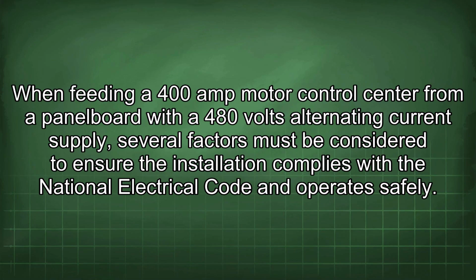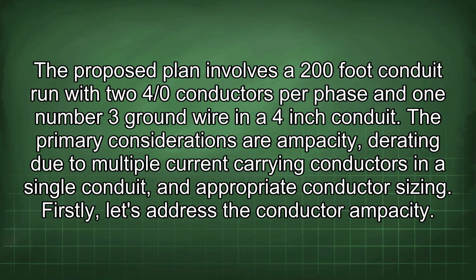When feeding a 400 amp motor control center from a panel board with a 480 volts alternating current supply, several factors must be considered to ensure the installation complies with the National Electrical Code and operates safely. The proposed plan involves a 200-foot conduit run with two 4/0 conductors per phase and one number 3 ground wire in a 4-inch conduit.